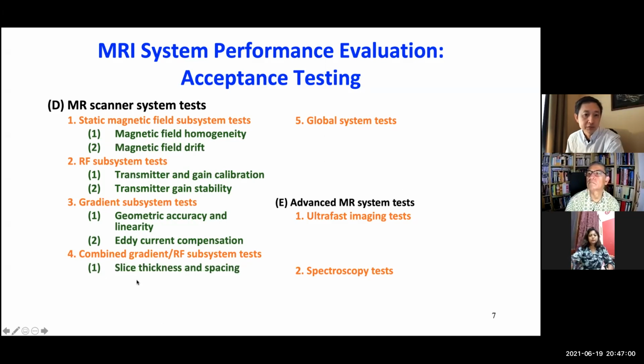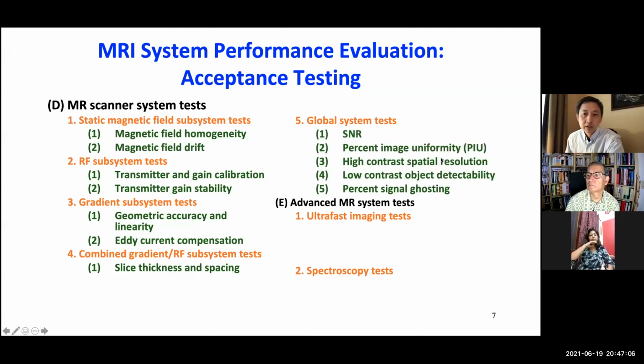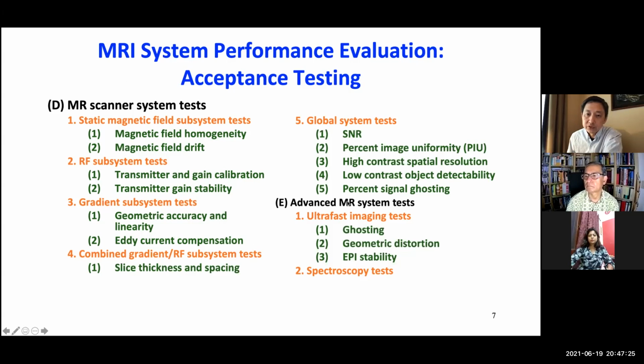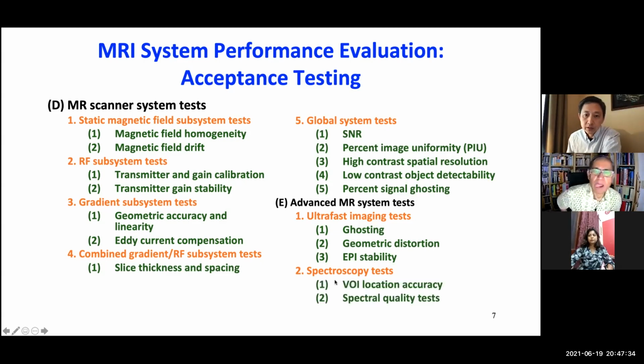This is typically measured during the service, the regular preventive maintenance. For the combined gradient and RF subsystem, mainly that's slice prescription, so slice thickness and spacing. For global system testing, those include signal to noise ratio, percent image uniformity, high contrast spatial resolution, low contrast detectability, and percent signal ghosting. And for the ultra-fast, those are advanced applications. Ultra-fast imaging includes ghosting, geometric distortion, EPI stability, and spectroscopy, including VOI, volume of interest, location, accuracy, and spectral quality test.